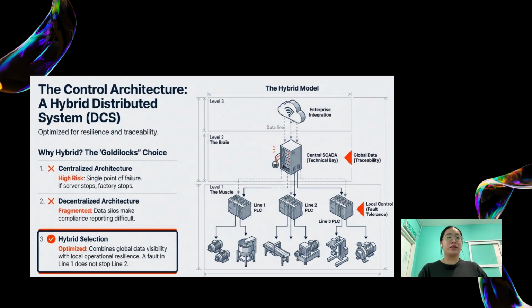Let's look at the control architecture. We selected a hybrid DCS model. We call this the Goldilocks choice because it solves two major engineering risks. First is avoiding single point failure. Unlike a purely centralized system where a server crash stops the factory, our local machines at level 1 maintain fault tolerance. A fault in line 1 does not affect line 2.